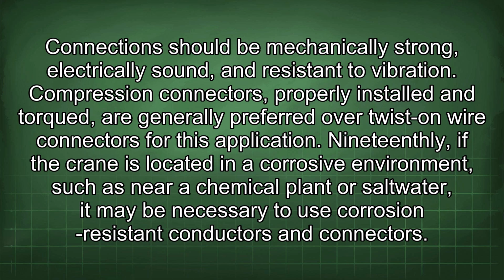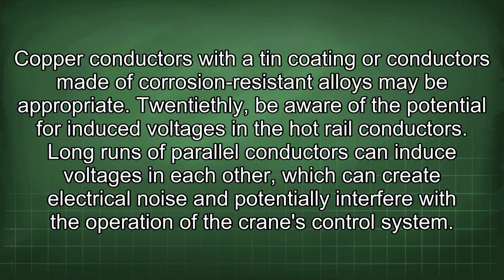19thly, if the crane is located in a corrosive environment, such as near a chemical plant or saltwater, it may be necessary to use corrosion-resistant conductors and connectors. Copper conductors with a tin coating or conductors made of corrosion-resistant alloys may be appropriate.